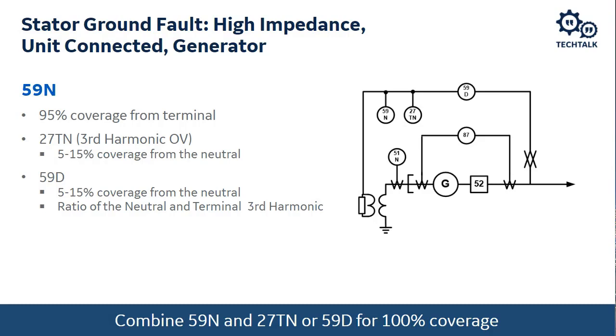The issue with the 59N here is that it's not going to provide us 100% coverage for faults within the generator. When we talk about 100% coverage, a fault at the terminal is basically 100%. Then a fault at the neutral of the transformer is 0%, because a fault at the neutral is effectively just another ground within the same ground, and you're not going to get any ground fault current. With the 59N, because of the accuracy of the relay, and especially the accuracy of the VT that we're measuring, we're not going to be able to reliably detect ground faults close to the neutral of the transformer. It might give us very good coverage for about 90% of the generator, from the terminal to about 90 to 95% toward the neutral of the generator.